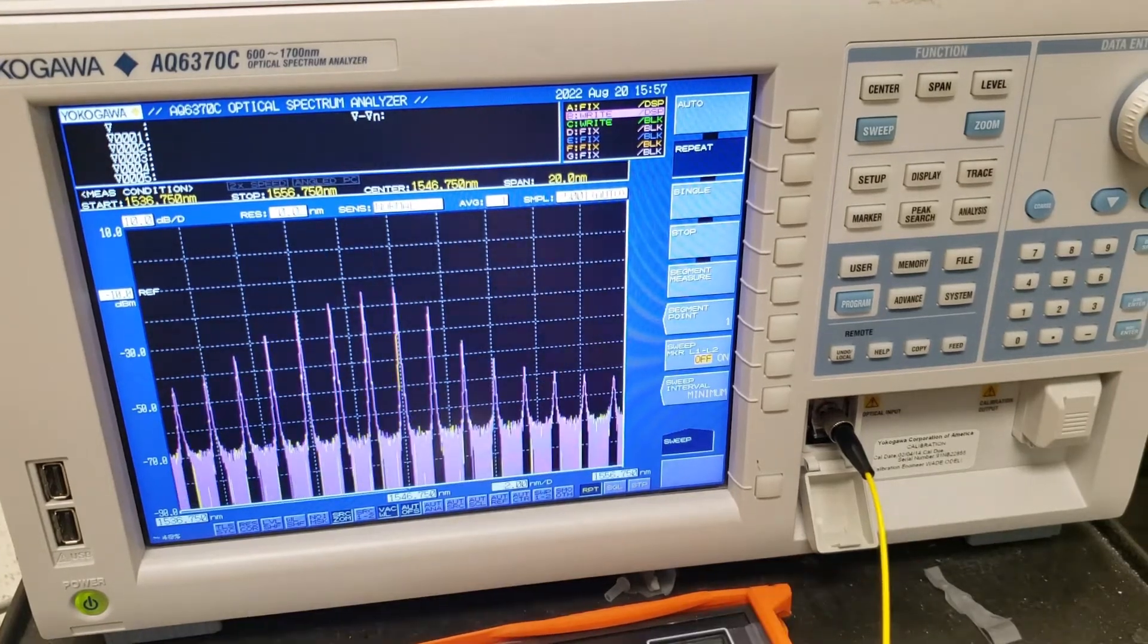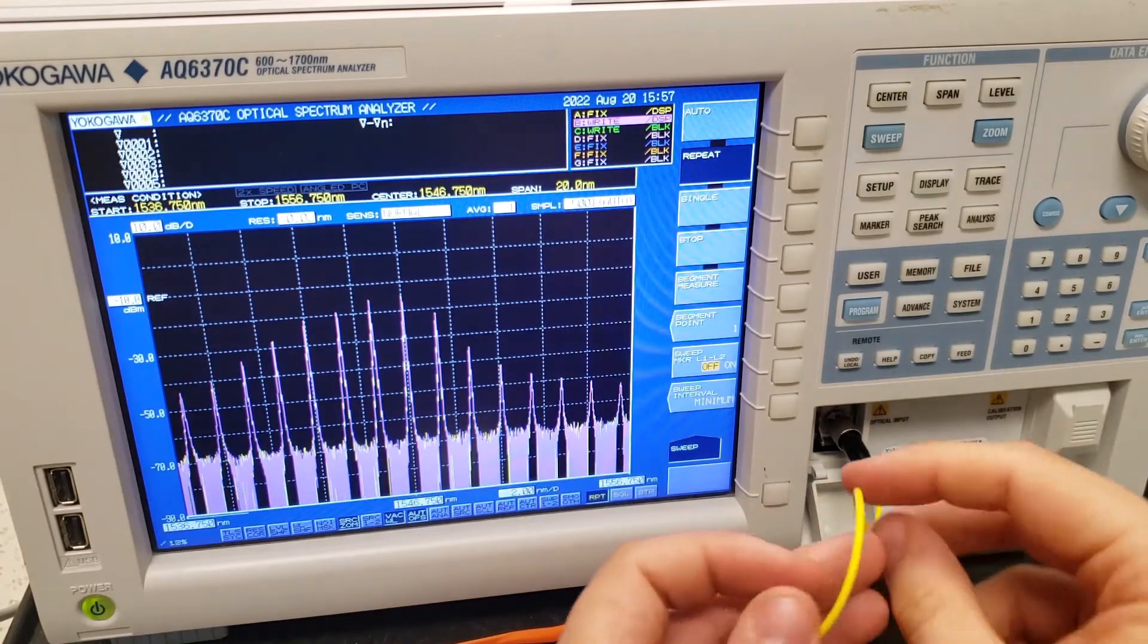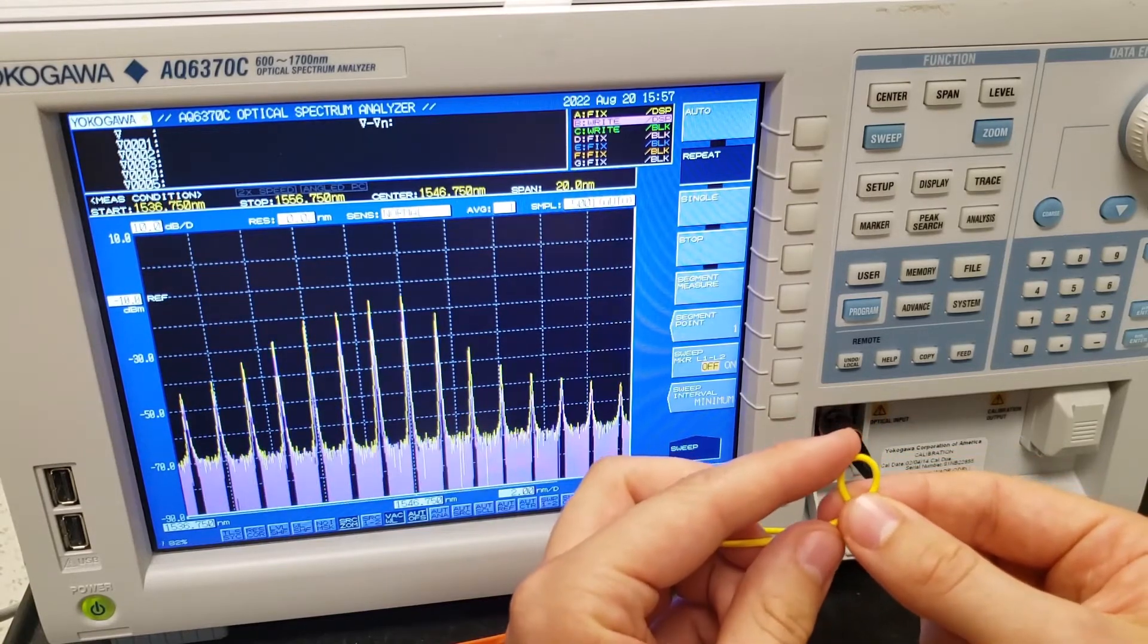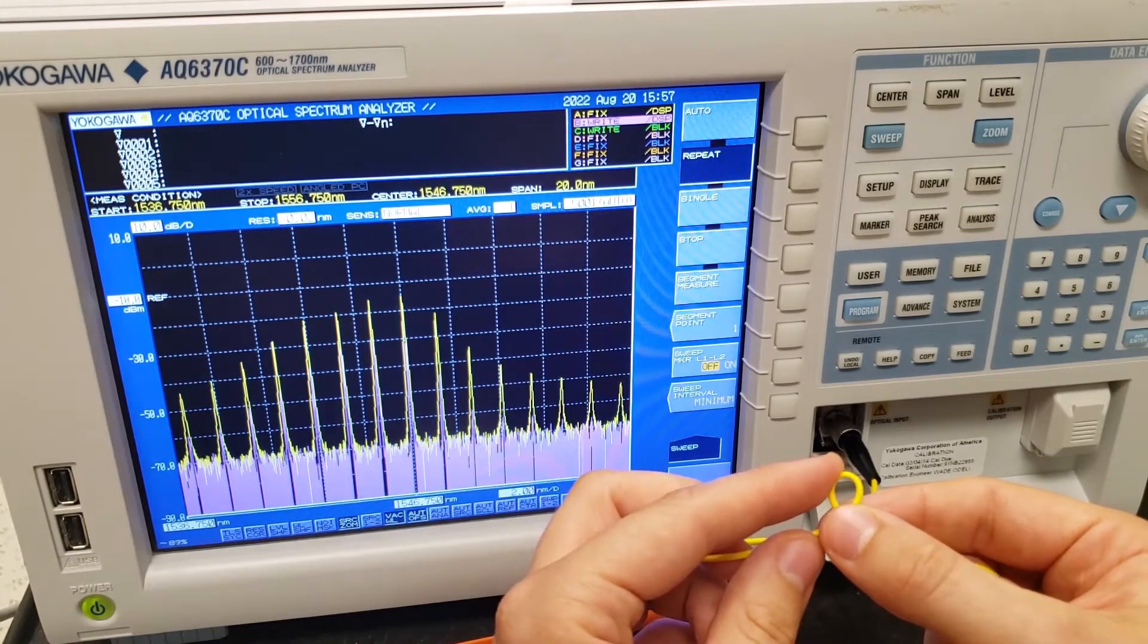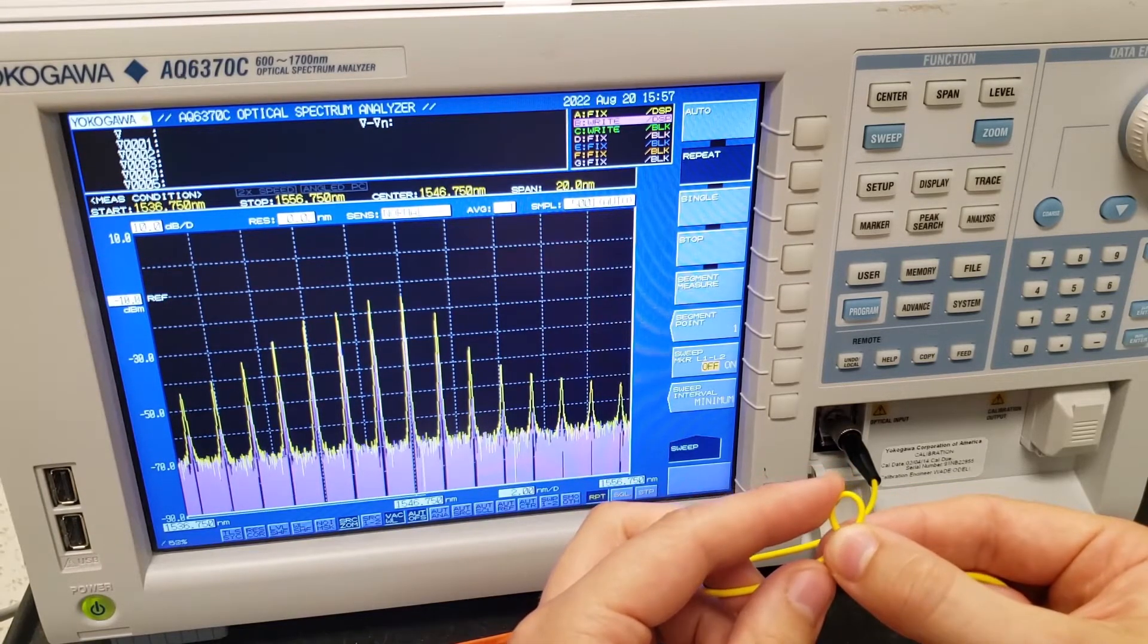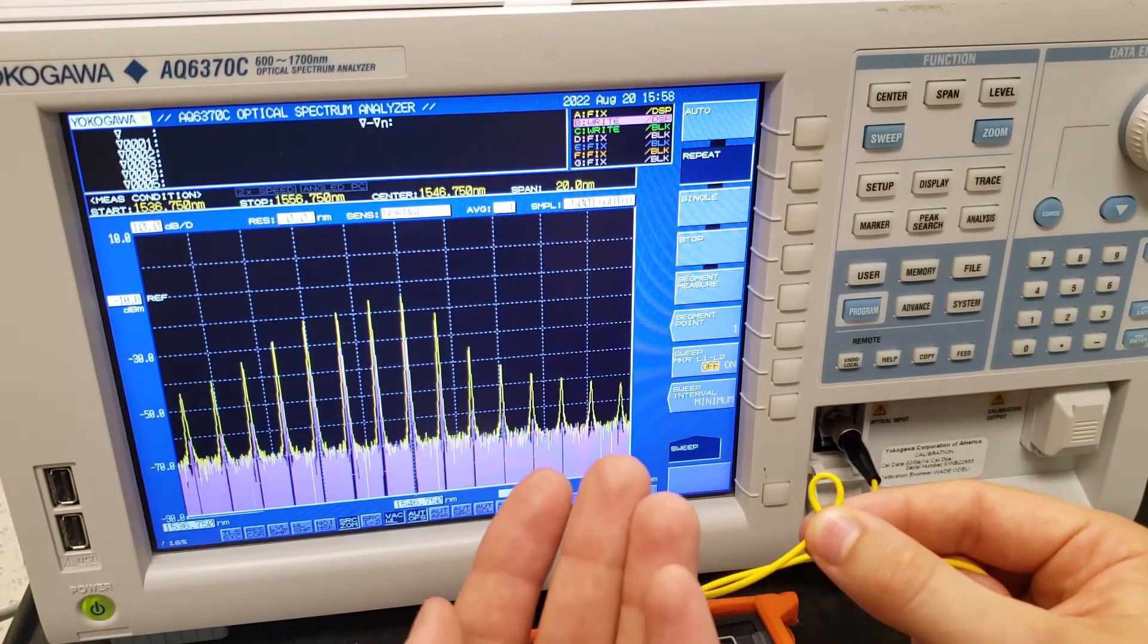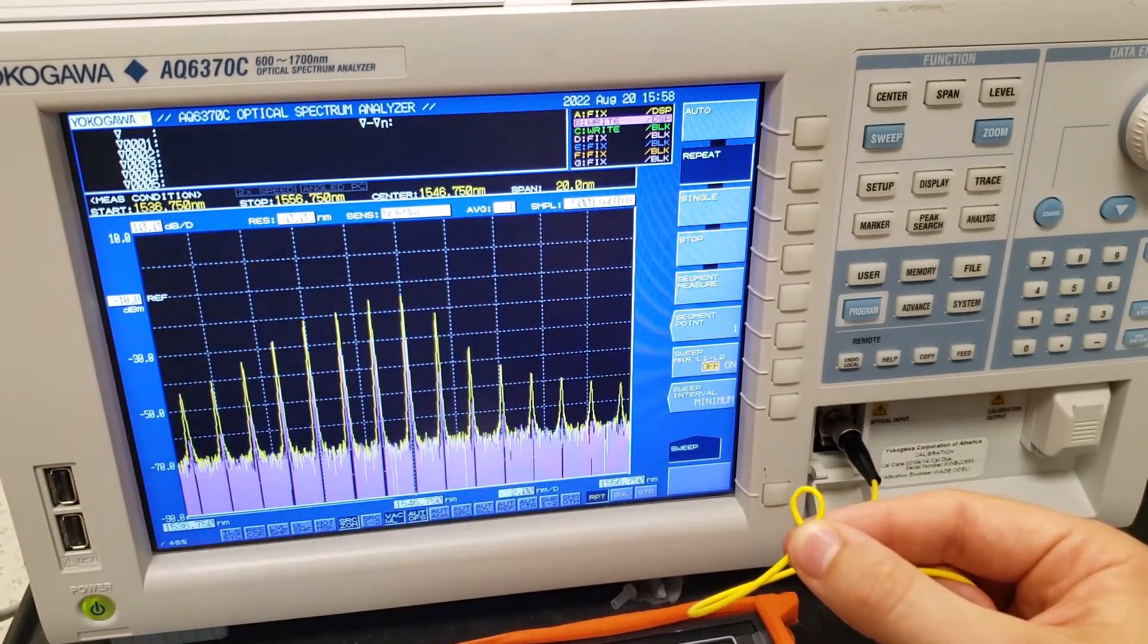Now of course the real advantage of an optical spectrum analyzer, or an OSA as we also call it, is that you can measure multiple wavelengths and their individual strengths individually. So let's see what happens if I bend this fiber. We should be able to see that all of the purple lines begin to decrease. This will also tell us if there's some kind of wavelength-dependent attenuation. Suppose that maybe this kind of bending is stronger for higher wavelengths than lower ones, then we'll be able to see that they get decreased much more than the ones over here.